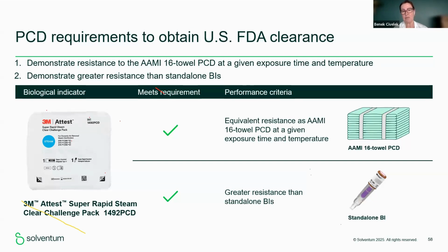The second was with a more fractional vacuum, so we expect worse conditions. We see that both the PCD BI/CIs and also the towel pack, which we place there, have the same positive BIs and fail CI results. Also, a clinical testing was done. And the second part was to show if this system, this PCD, is showing greater resistance than a standalone BI. So when they made the test with a fractional vacuum, they see that the PCD is capturing the challenging results.